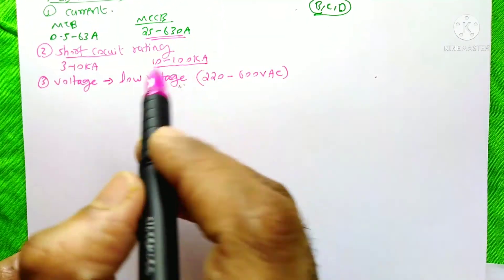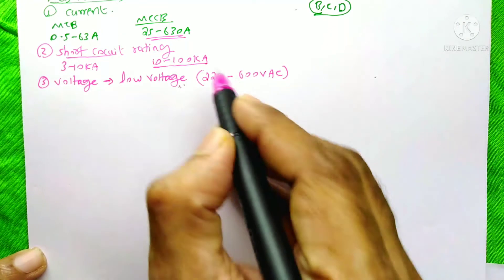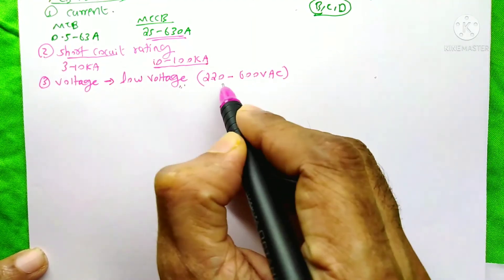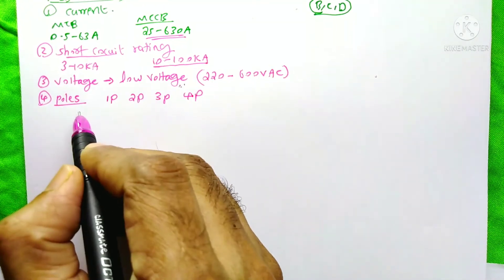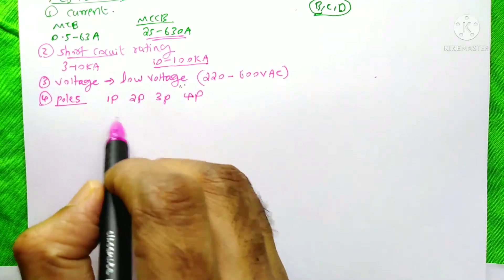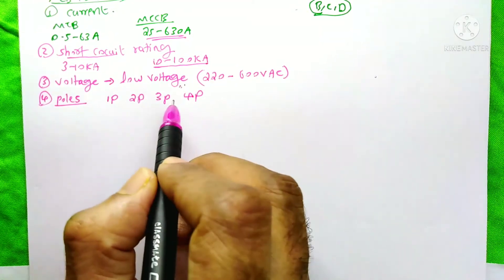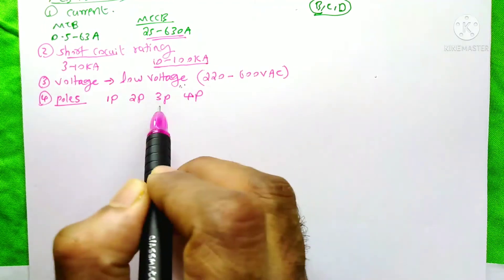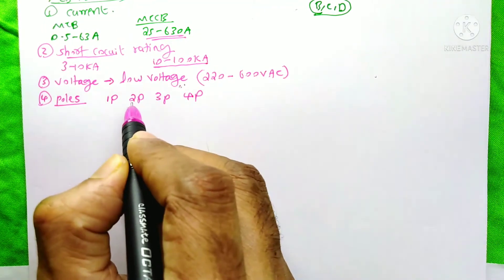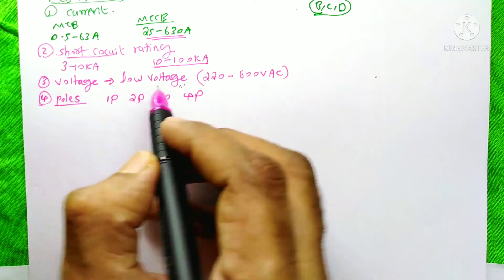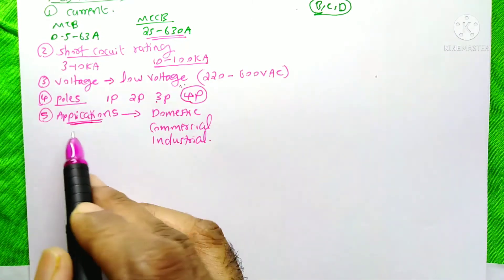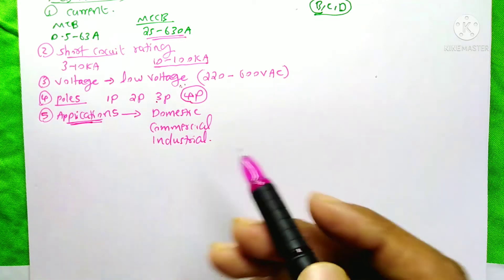The next factor is voltage. Both MCB and MCCB are low-voltage devices, operating from 220 to 600 volts AC. The next factor is the number of poles. Both MCB and MCCB are available in single pole, double pole, 3-pole, and 4-pole configurations. Single pole and 2-pole are only applicable to single-phase circuits, while 3-pole and 4-pole are for three-phase circuits.